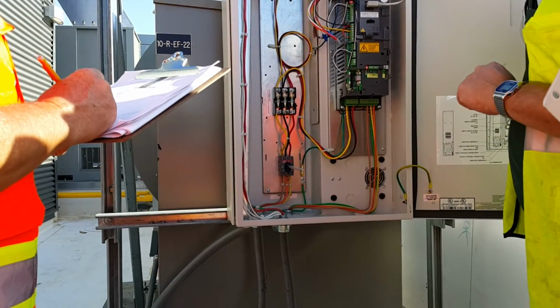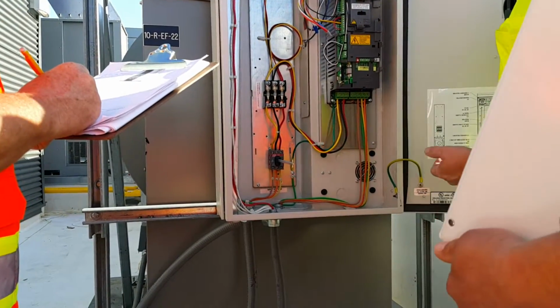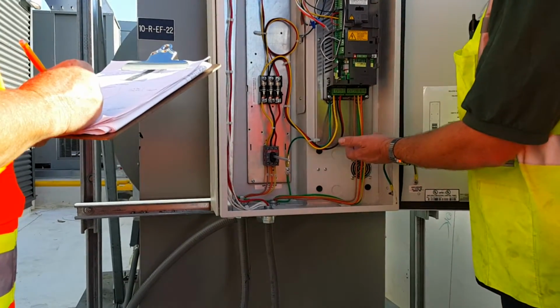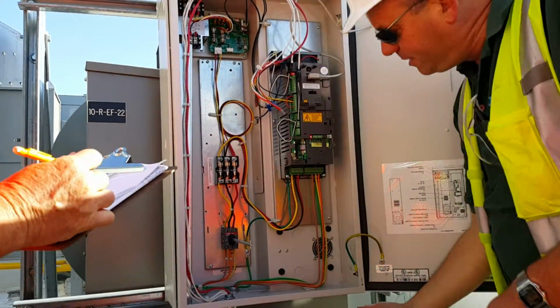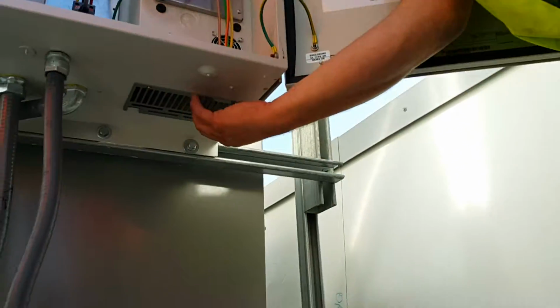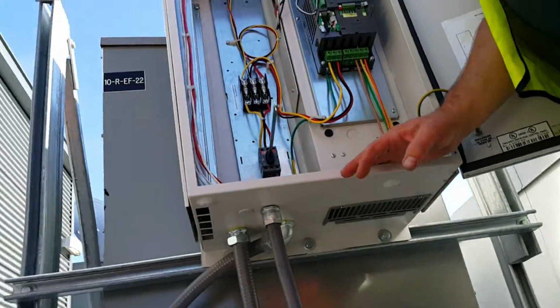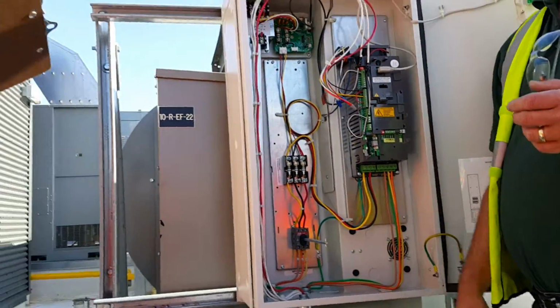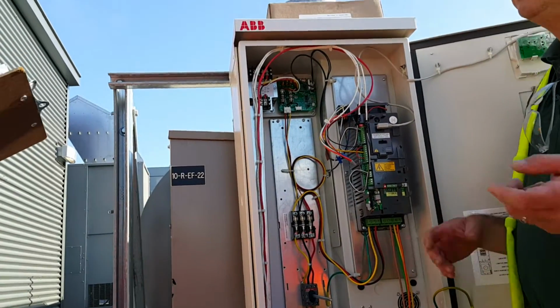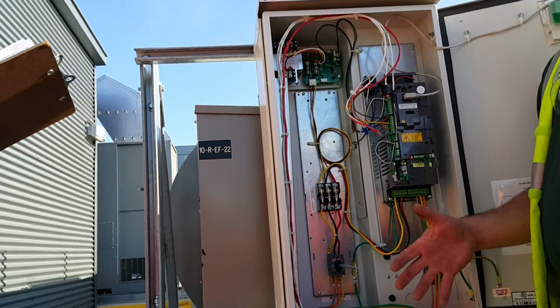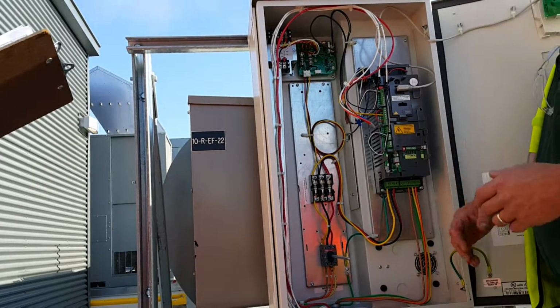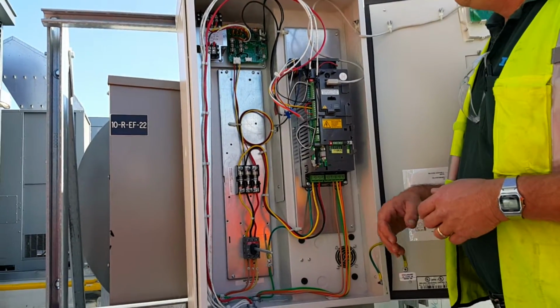The next thing on these units, or not on all units, is you want to be able to once a year clean out the heat sink. In this case, you've got to take this plate off right here and go up there with some air. You know, the canned air stuff doesn't have enough power, and it's also stupid expensive. I use a little shop vac, reversible, blow up in there, get that stuff out of there.